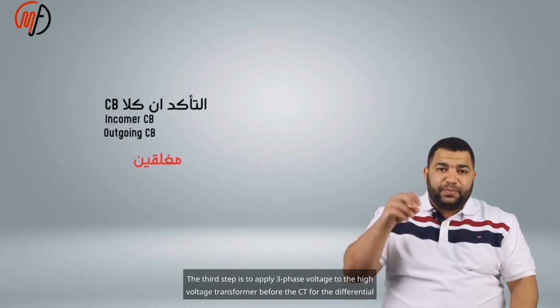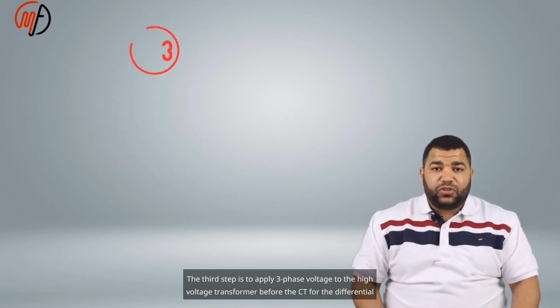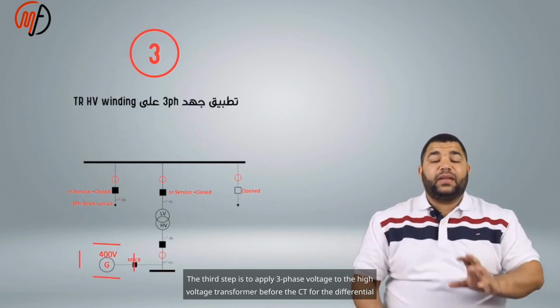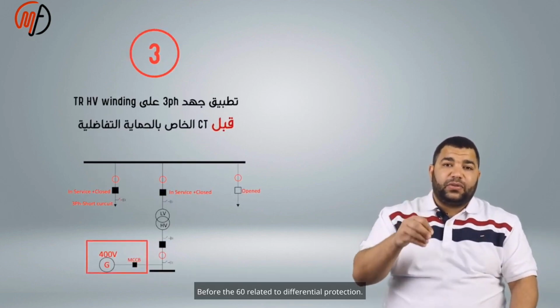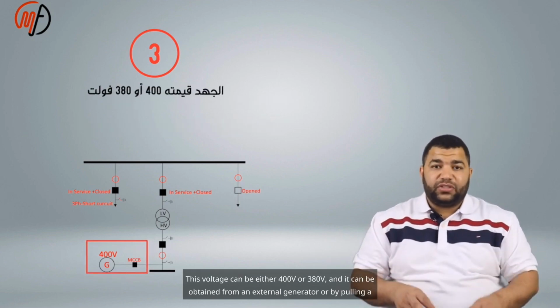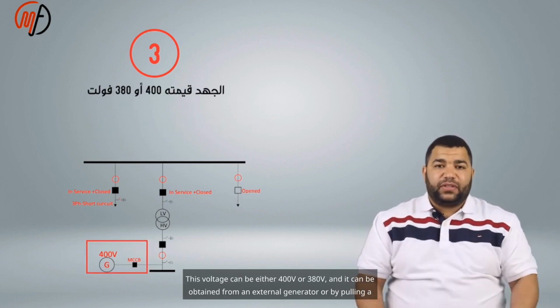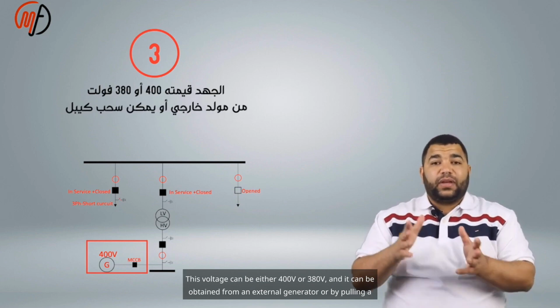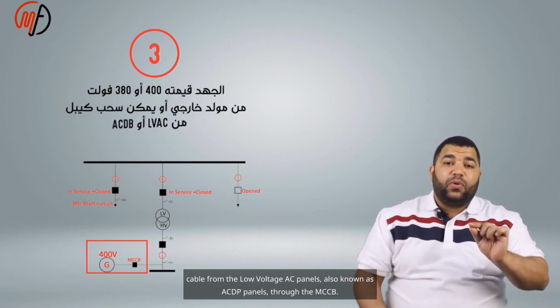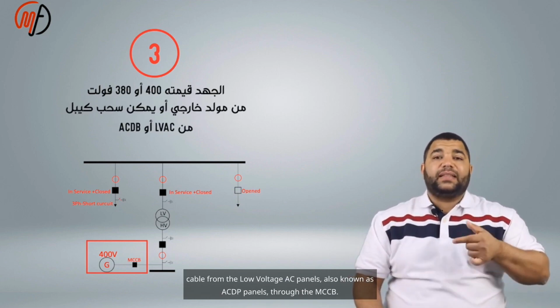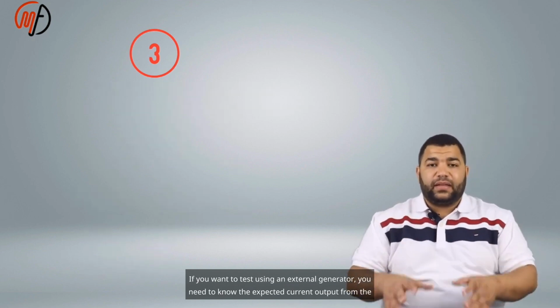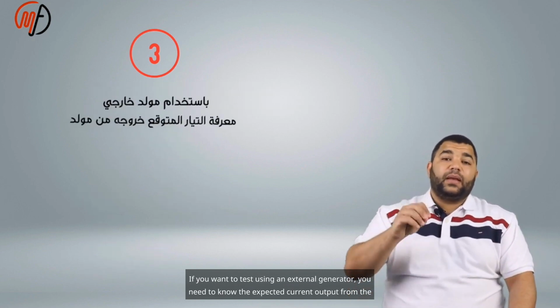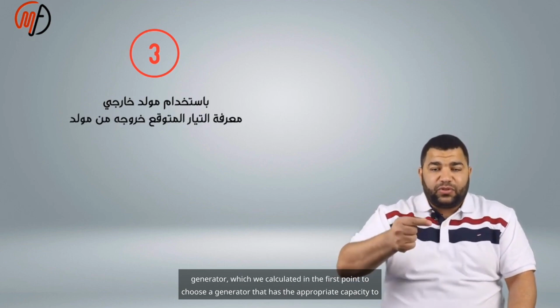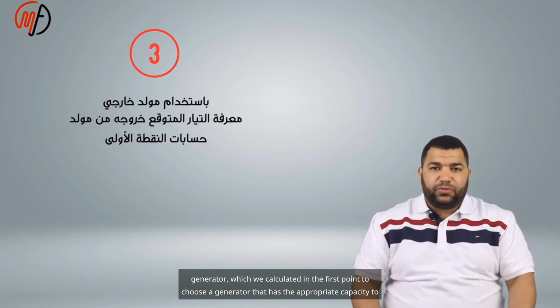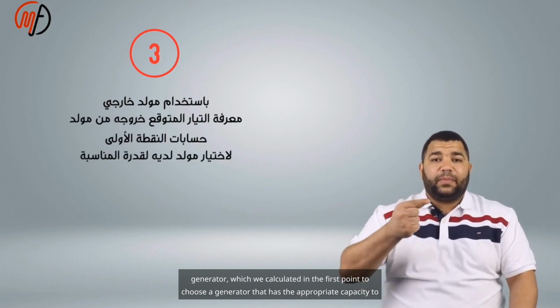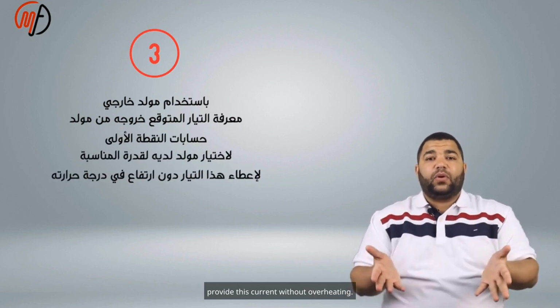position. The third step is to apply three-phase voltage to the high voltage side of the transformer, before the CT for the differential protection. This voltage can be either 400V or 380V, and it can be obtained from an external generator or by pulling a cable from the low voltage AC panels, also known as ACDB panels, through the MCCB. If you want to test using an external generator, you need to know the expected current output, which we calculated in the first point, to choose a generator that has the appropriate capacity to provide this current without overheating.